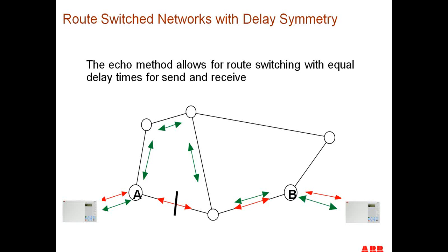That works just as long as the path from terminal A to B and B to A is the same. But as soon as I start switching and I get a path from A to B that's not symmetrical, and it follows some other path the other way instead, you can see that the time it takes to get from A to B and the time it takes to get from B back to A is not the same. So if I set my relay based on the time it takes from A to B and B to A divided by 2, I would have the wrong information. So there are limitations on how much channel delay you can tolerate.